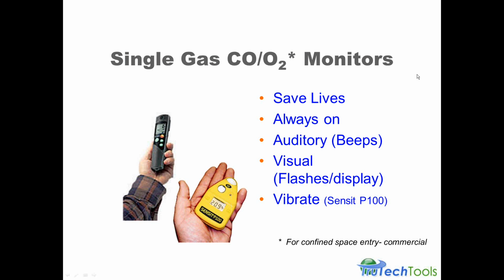We did talk about personal monitors for CO and even oxygen for confined space entry, and this can be true in commercial situations when you have oxygen deprivation. But they're very good to have on hand. They'll help you save your life or the life of someone you're working with, or the property you're working on. Many of them you can keep always on. Some of them, like the Sensit P100, have a very long battery life, basically 2 years you can keep it on. They give auditory and visual flashes or beeps, and the Sensit does happen to vibrate to give you that physical interaction that you do have an alarm situation happening. And as we mentioned before, the reading on the display can be used to help you understand if your area is safe to power up your meter to get your background or zero out your CO sensor.